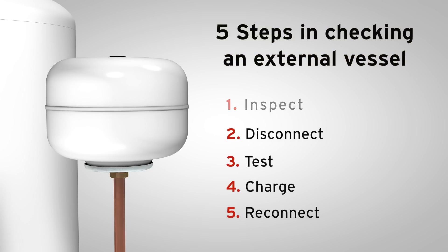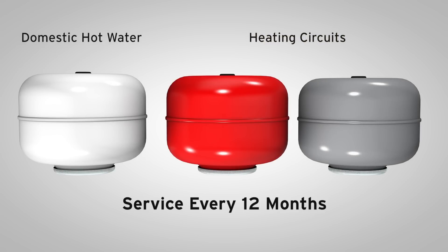Heating systems with unvented cylinders usually have two expansion vessels: a white one protecting the domestic hot water circuit and a red or grey one for the heating circuits. It is important that these are checked and serviced every 12 months.